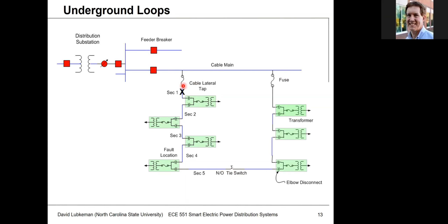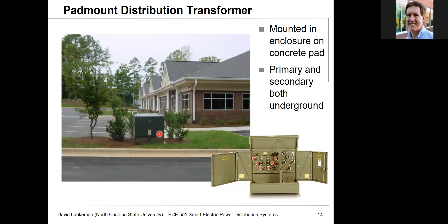And so for example, if I were going to lose this cable, what I can do is unplug the cable here, unplug the cable here, and then I could feed this customer through this tie switch by actually closing it. And so a lot of times underground is actually set up in a loop. There's actually two connection points for underground. So the transformer we would use for this would be what's sometimes referred to as a pad mount distribution transformer, where there is the three-phase connection maybe coming from the primary, then you have the three-phase connection going to the next transformer location. And these are located typically on pad mount concrete pads.